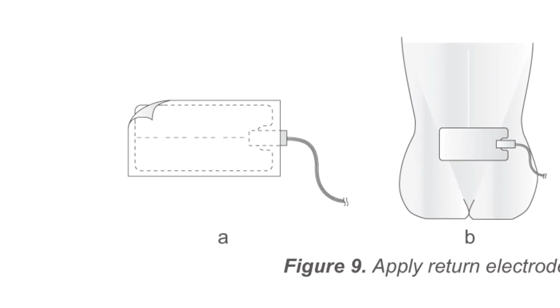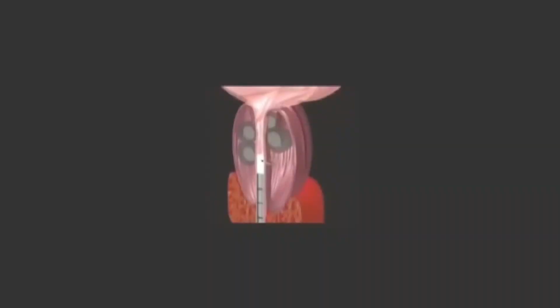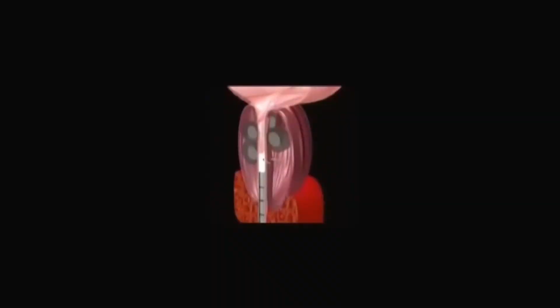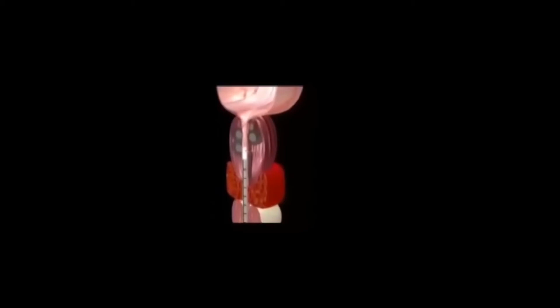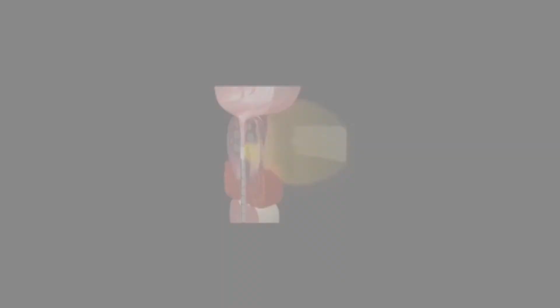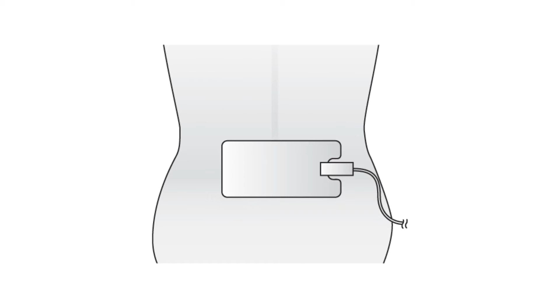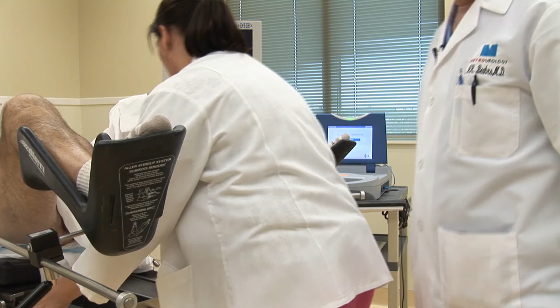The return electrode also has a split electrode design, which is required for the radio frequency generator's neutral electrode monitoring, or NEM circuit. The NEM circuit monitors the impedance between the electrode halves. This provides a measure of how secure the electrode is attached to the patient's skin. The return electrode's design and monitoring help to reduce the risk of possible patient injury. After the electrode is attached, the nurse will drape and catheterize the patient.